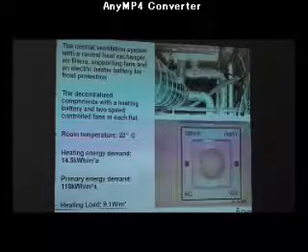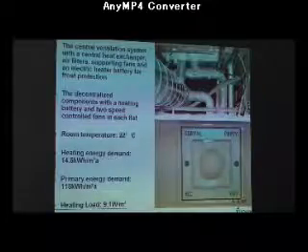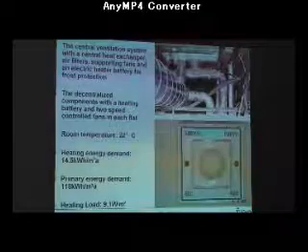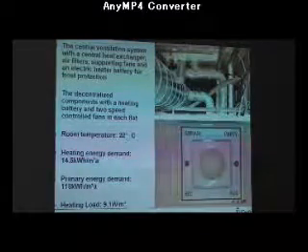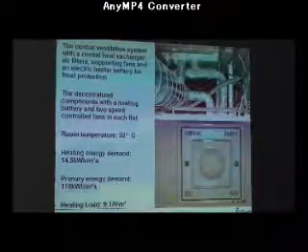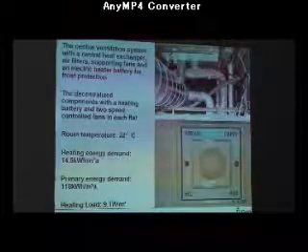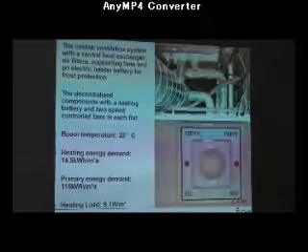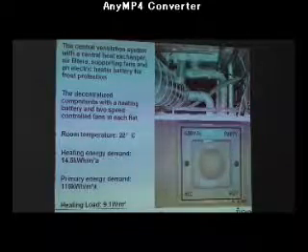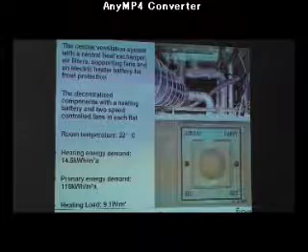And each family can choose different ventilation modes by switching the control panel according to their own requirements. And the measurements show that if the room temperature was kept at 22 centigrade, the heating energy demand is 14.5 and the primary energy demand is 118. So these figures completely meet the requirement of passive house.